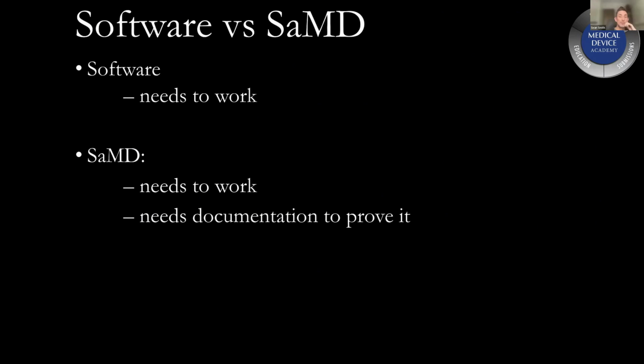One of the things I've been trying to teach people is that in your Scrum team meetings, and a lot of people are using Scrum teams, your backlog should include the documentation. You do not have to review, approve and bless it and make it holy. You just need to have it as a draft, just like the software. The software, you iterate multiple times and keep improving it. We have a minimum viable product and finally a final version we deliver to the customer. Same thing for the documentation. You can iterate many, many times and deliver those pieces as you go and edit them. They don't have to be final approved versions until you submit to the FDA, and even the FDA may make you make some changes, like labeling. That's one of the things I try to teach them.